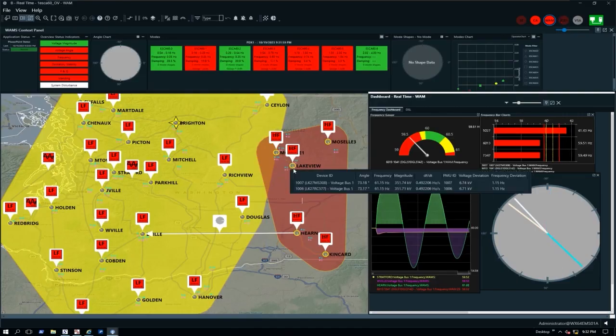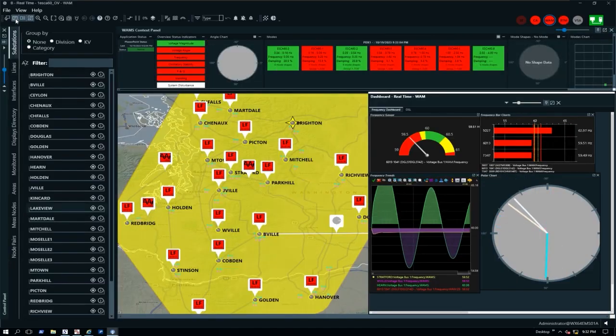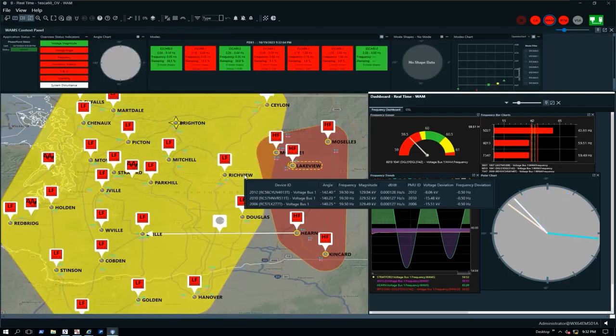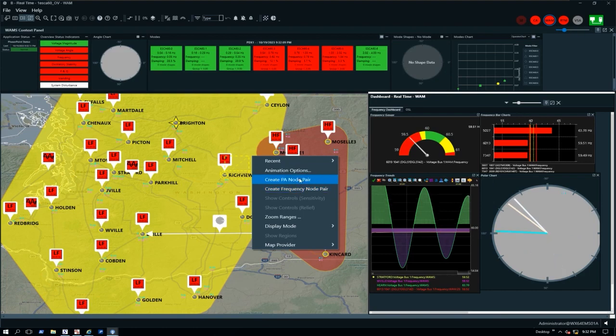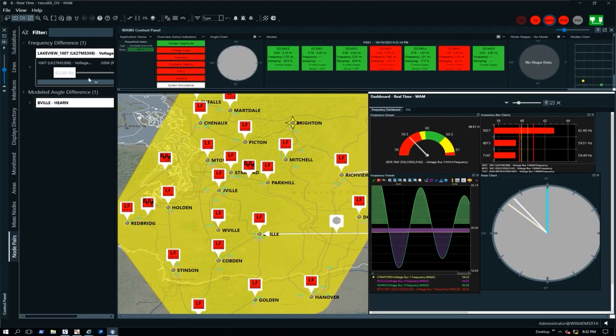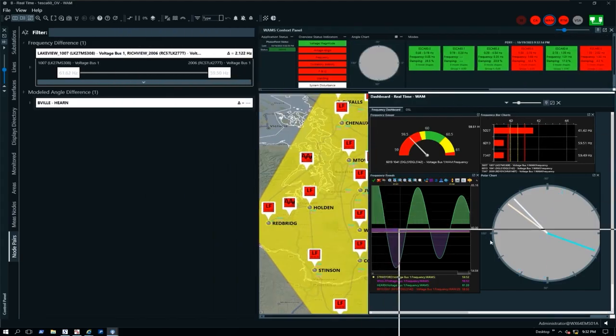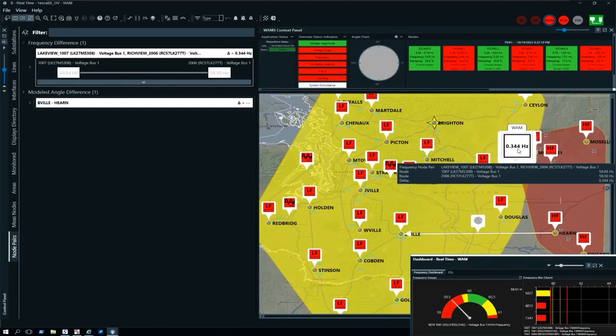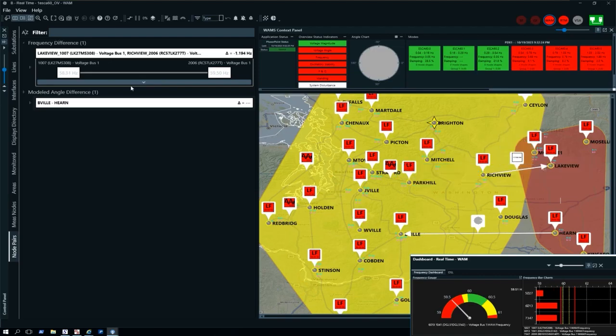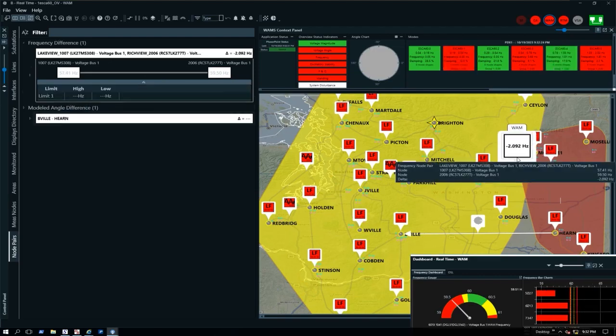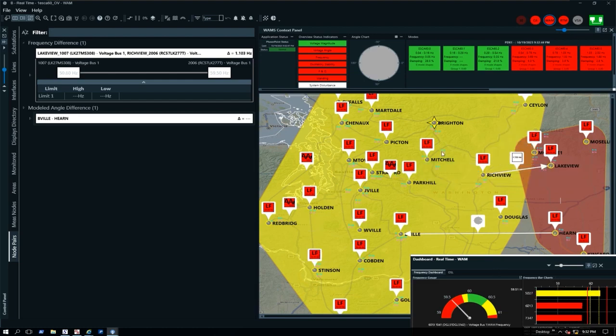We also have the ability to easily turn that off for a second if we wanted to compare a frequency node pair or a phase angle node pair. You can create those on the fly. It's going to tell me that I've got a phase angle difference here, and you can see it's rapidly changing between those two. So we want to get our frequencies within limits. We can set high and low limits on this frequency indication, but this is just another tool for your system operators to use to ensure that you've got the correct voltage in both islands across that open corridor, and that your frequencies are matched up across that open corridor before you ever try to close this path back in. That's going to ensure that you don't end up with a large power inrush that would potentially collapse that smaller island.